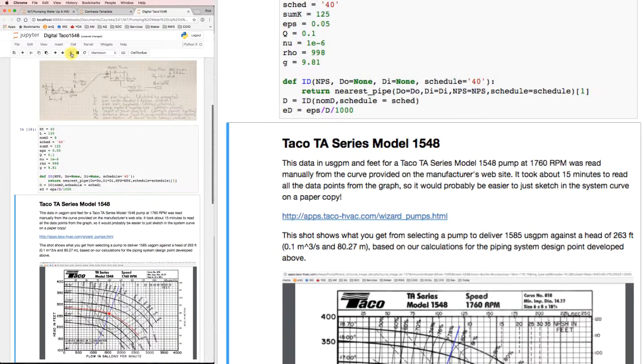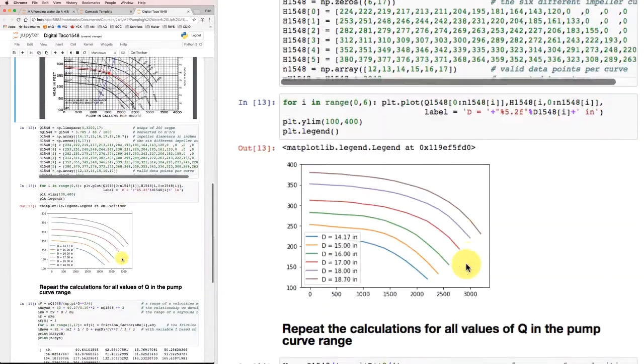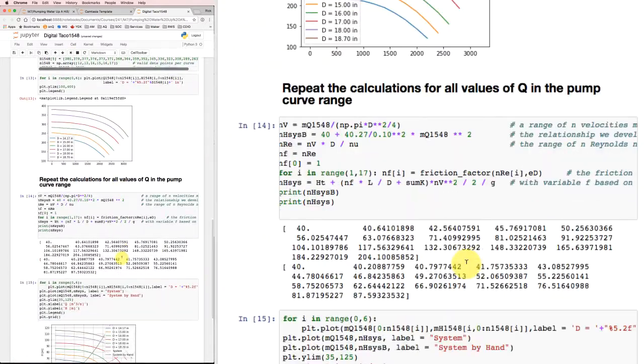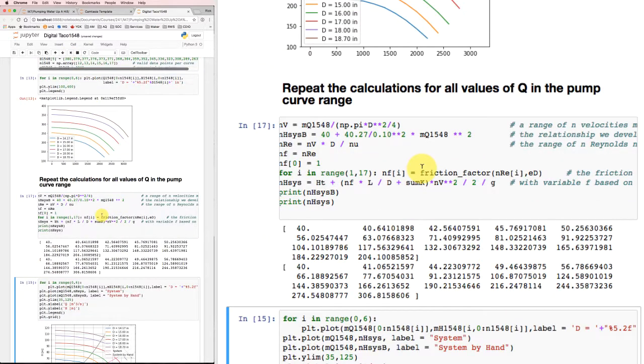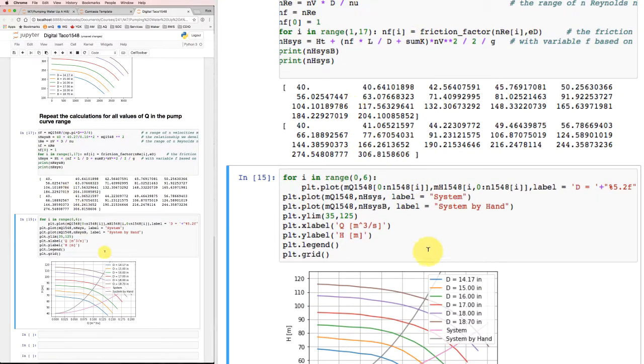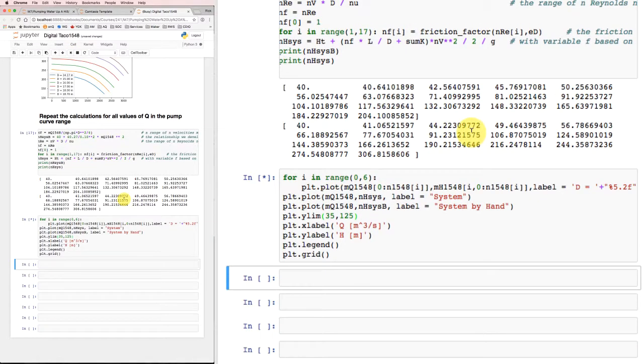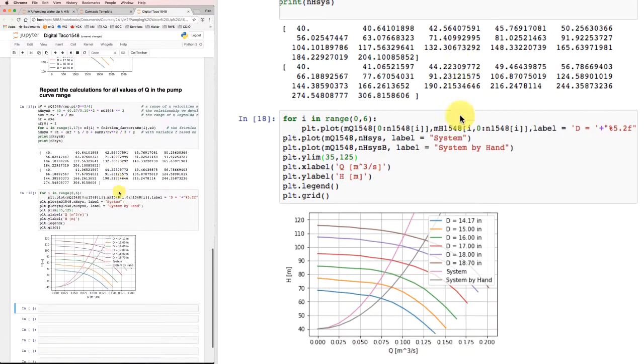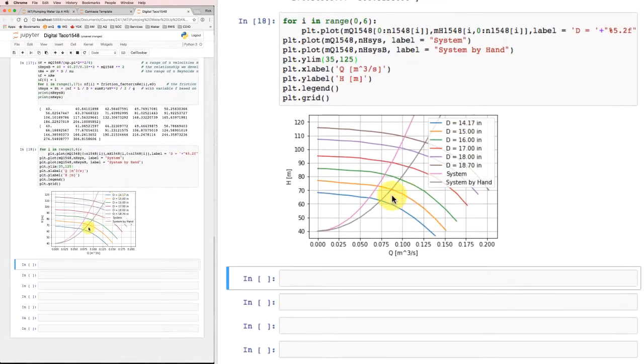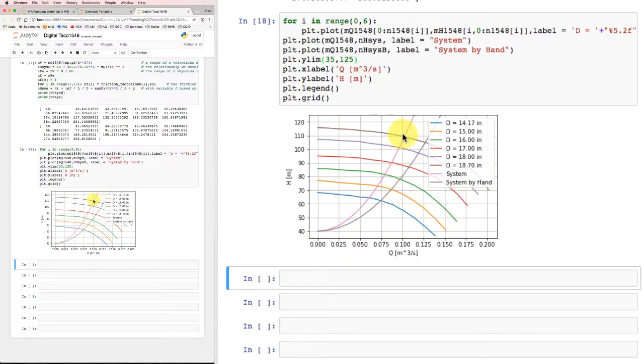So suppose this minor loss coefficient went from 15 up to say 125. Well, let's see what happens if we do that. I can go down here now and I can do my calculations over again and I'm back up to having quite a large head loss coming out of my system. When I do the plot, now I can see I'm getting a larger head loss here than I was before. But by closing down the valve, I've reduced the amount of flow going through the system.